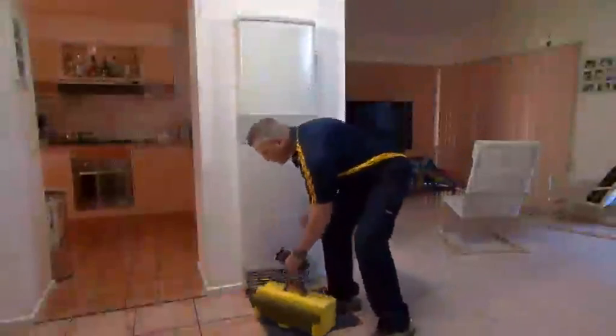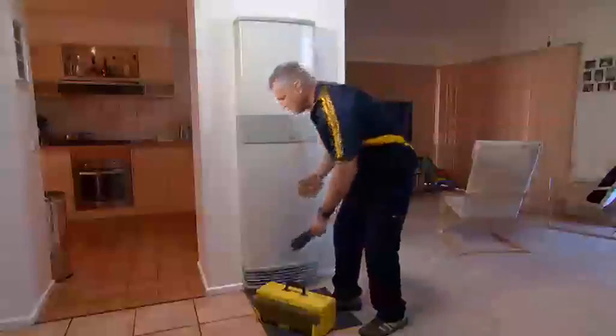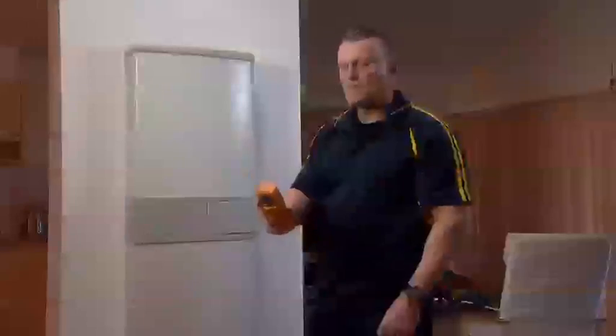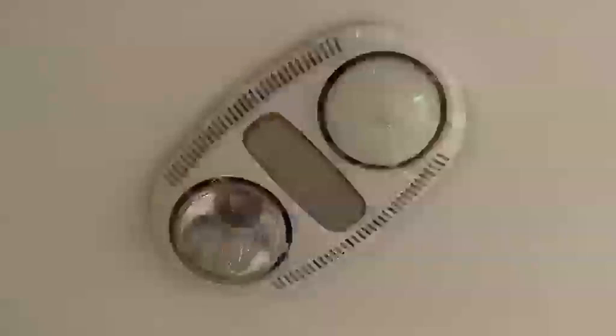Testing for carbon monoxide gas from open flued gas appliances must be carried out in two stages. First, test for spillage with only the appliance operating, and secondly, test for negative pressure flue gas drawback by turning on any extraction fans within the building. Don't carry out these tests together because you will not know whether the fault lies with the appliance installation or is caused by negative pressure when exhaust fans are run.